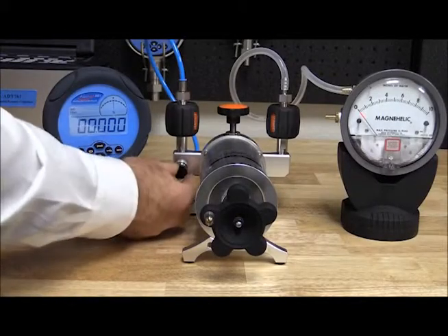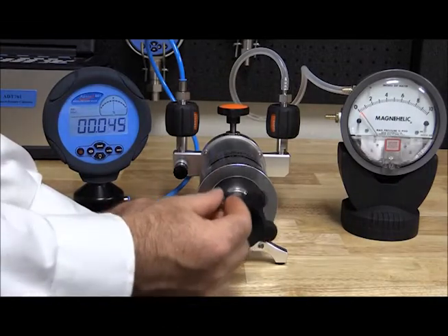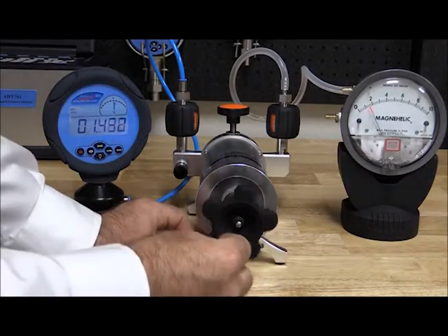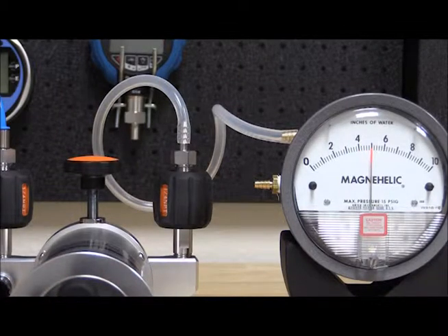Now we are ready to generate pressure and record our results. Typically three to five points are taken both ascending and descending. By taking more than two points, we are able to check the gauge's linearity and hysteresis.